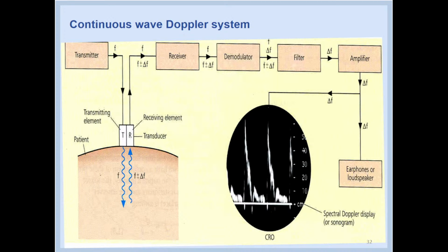Certain Doppler shifts have a characteristic sound. For example, the fetal heart Doppler shifts sound like galloping horses. The placenta sounds like wind rushing through trees. The experienced ear can recognize any abnormalities of the Doppler shift's sounds. On the other hand, the Doppler shifts, delta f, can be converted directly into velocity using that equation that was shown.